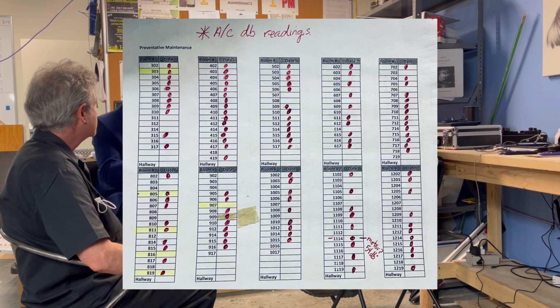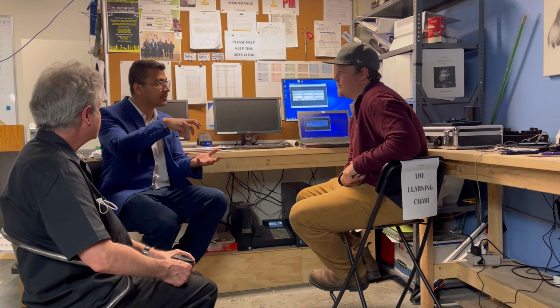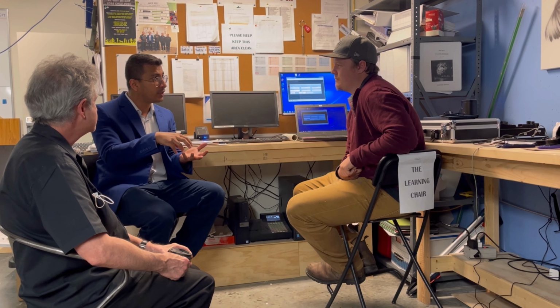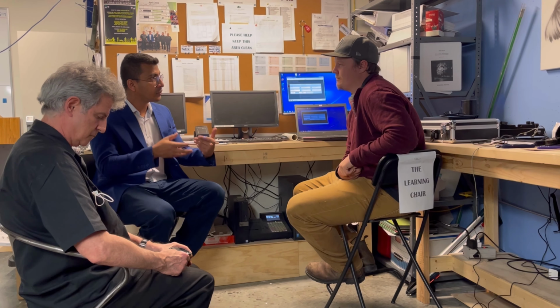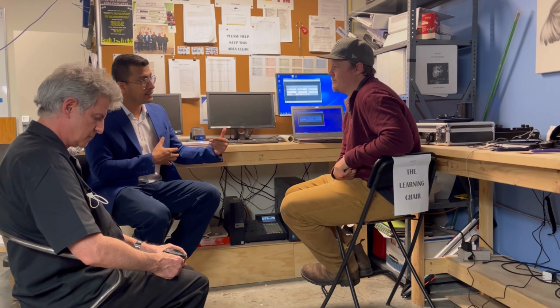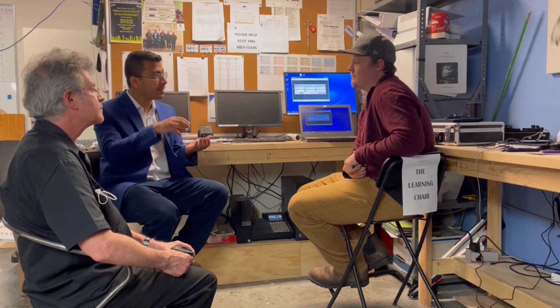Let's consider a scenario: if the 4 rooms connected to one branch box are noisier than the other ACs on the same floor, do you think that branch box might be failing? Is there an EEV valve on that branch box? Each branch box has several solenoids and several EEVs for each connected branch.